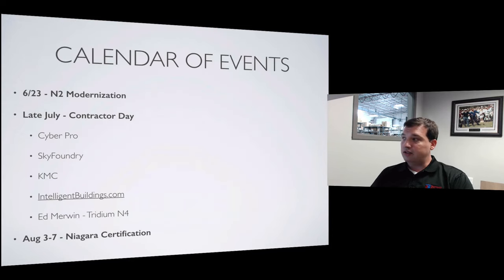All right, calendar of events. For you Johnson Controls guys, we've got the N2 modernization coming up on June 23rd. Johnson Controls just came out with their PC controllers with the N2 embedded in them. So this is pretty neat. You can take a PC controller, the PCVs, PCGs, and PCAs, and they can be N2 or BACnet with just a firmware reflash. So what you'll see a lot of times, if you go into a building with N2 in it, you can install a new controller and just leave it N2. Then over the next few years, as those original N2 controllers go bad, replace them with new controllers. Once you've got them all replaced, you just do the firmware flash to all of those controllers, and now they're all BACnet. Just a new, easier way to do things.